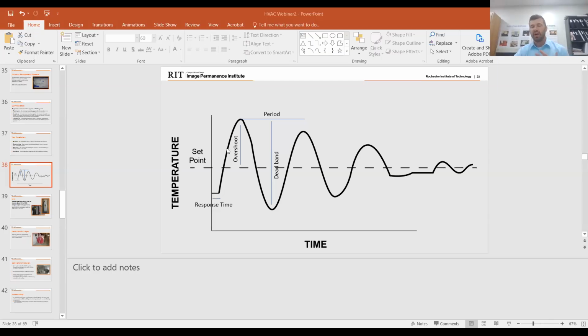Let me see if I can bring that slide back up. The deadband is going to be with the way that our HVAC system needs to function, for lack of a better term. Some of the older thermostats are going to be aiming for that dead band. Got it. Okay, so let me share my screen now. So some of the older HVAC systems aim for this overshoot. They're going to have that overshoot built into them, and the deadband is going to be almost a natural function in there. So for older systems, it is an inherent evil. For some of the newer systems, they can operate better, especially with, as I said, the newer smart thermostats, to try and undo that, to try and phase them out, if you will. Does that answer that? Yeah.